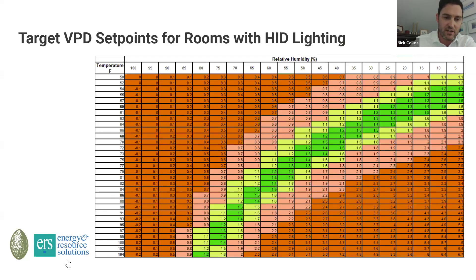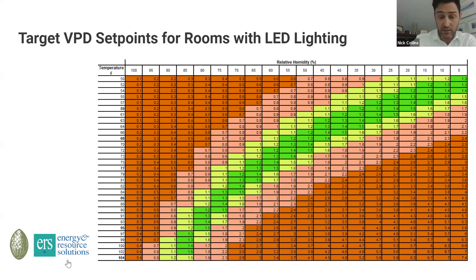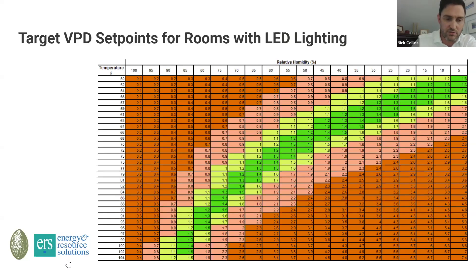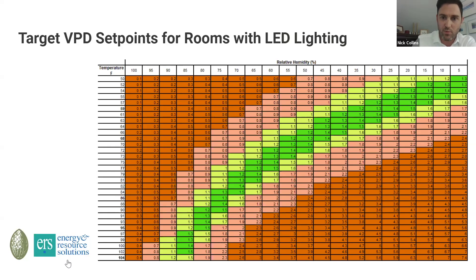This chart here is dependent on what I entered as a leaf surface temperature for HID fixtures. Moving to the next slide, this is a VPD chart for an LED setup, where we're accounting for the fact that we no longer have the same leaf surface temperature. This comes down to what Keith was talking about earlier — that reduction in sensible load moving from high pressure sodium, plus the change in spectrum. The reduced sensible load of an LED and its different, more targeted spectrum are going to impact the leaf surface temperature, which is another important element of vapor pressure deficit.